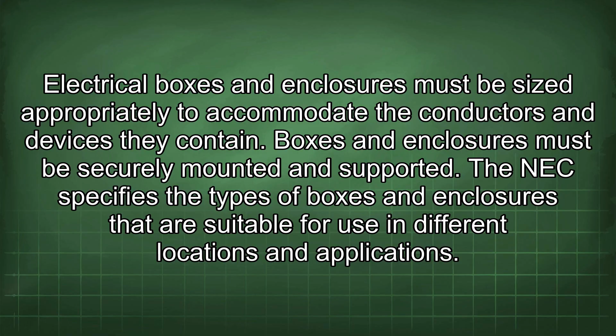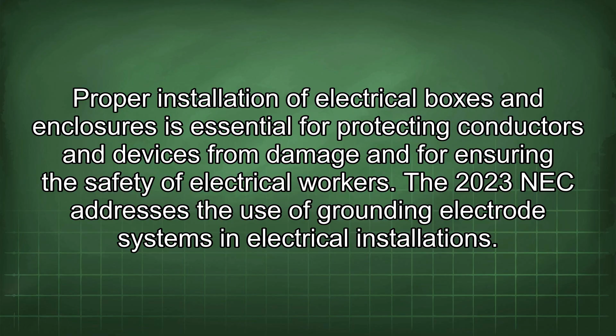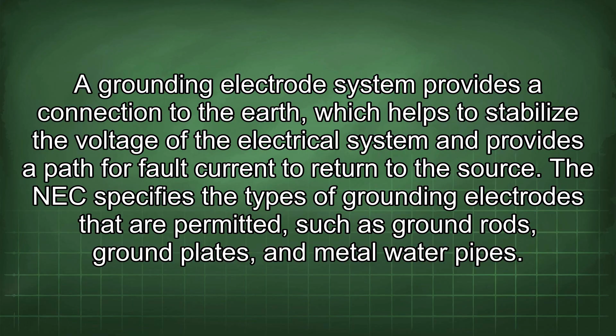The 2023 NEC addresses the use of grounding electrode systems in electrical installations. A grounding electrode system provides a connection to the earth, which helps stabilize the voltage of the electrical system and provides a path for fault current to return to the source. The NEC specifies the types of grounding electrodes permitted, such as ground rods, ground plates, and metal water pipes, and specifies the methods for connecting them to the electrical system. Proper installation is essential for ensuring safety and protecting people from electrical shock hazards.